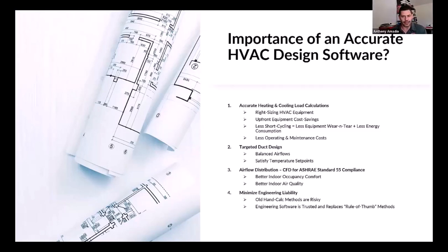But it starts right there: heat loss, heat gain calculations, and then right sizing the equipment based on those design temperatures, the indoor, outdoor, if we're talking heat pumps, air conditioning systems, and of course, even elevation. If we're talking, say, gas furnace heat, when we're up at high elevation, we lose some BTU. Okay, but we need to convert BTUs into CFMs. We do that by picking the equipment.